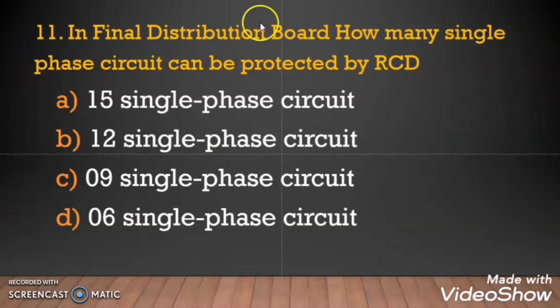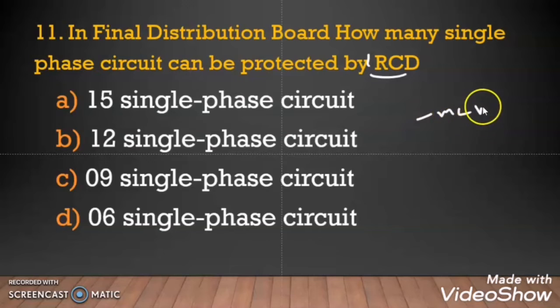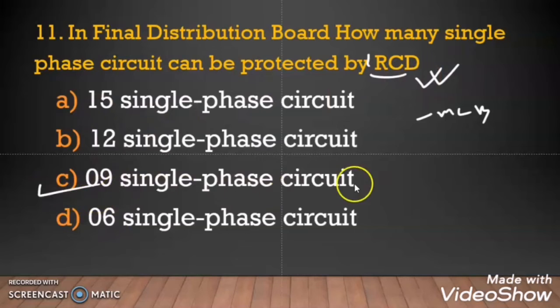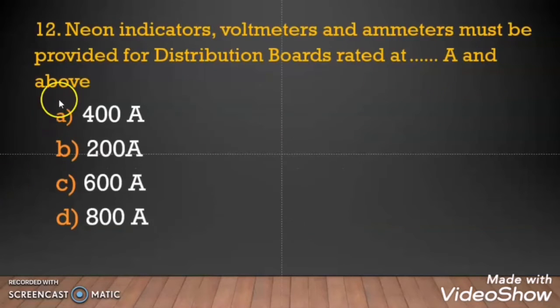Question 11: In a final distribution board, how many single phase circuits can be protected by 1 RCD? As per ADDC regulation, a maximum of 9 MCBs — meaning 9 single phase circuits — are allowed to be controlled by 1 RCD. So option C is correct.